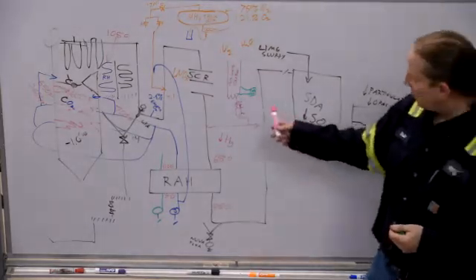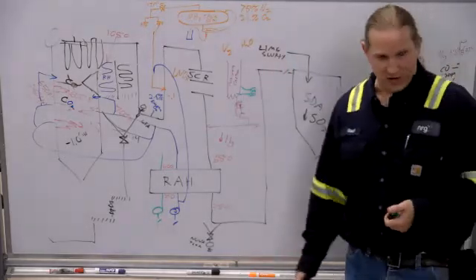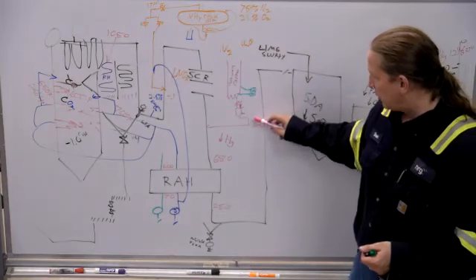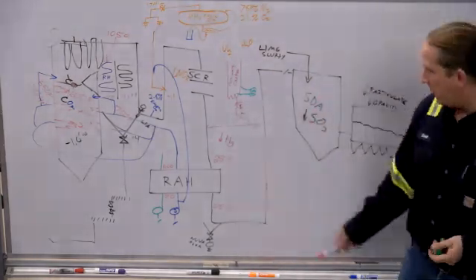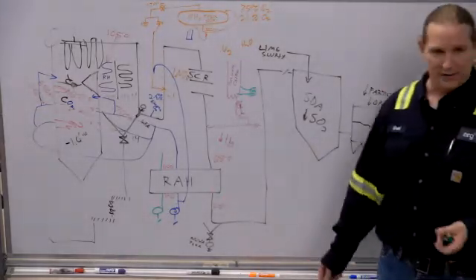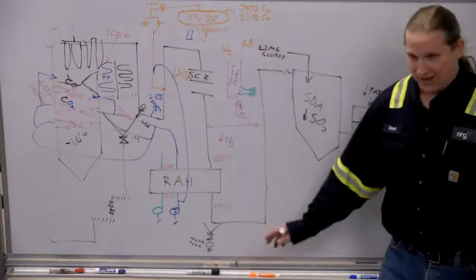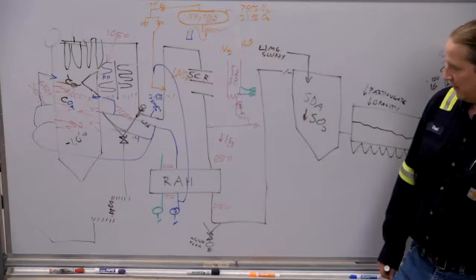If everything's working right, you might feel a tiny bit of vacuum on it, you might feel nothing on it. When these nozzles get clogged, then this blower will start to blow back up into there, and carbon will start to spew out into the room, and then carbon will be 2 feet deep in the room, and then we gotta figure out how to clean it. By the way, everything it touches goes ultra, ultra black. It's no fun to clean.